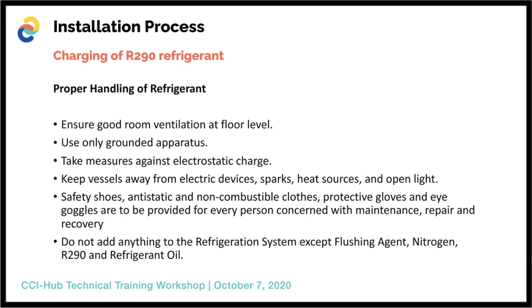Number two, use only grounded apparatus. Number three, take measures against electrostatic charge. Number four, safety shoes, anti-static and non-combustible clothes, protective gloves and eye goggles are to be provided for every person concerned with maintenance, repair, and recovery. Do not add anything to the refrigeration system except flushing agent, oxygen-free dry nitrogen, refrigerant R290, and refrigeration oil. And the next part will be turned over to Sir JP for the continuation of our installation process.